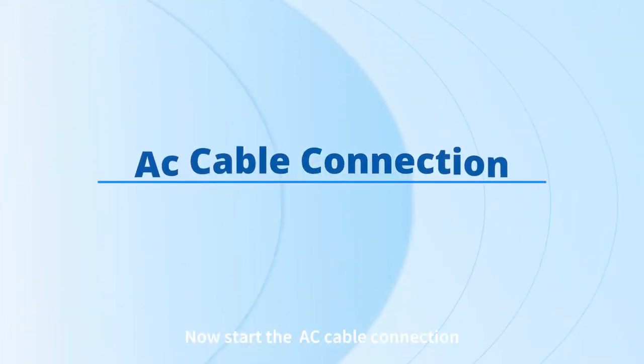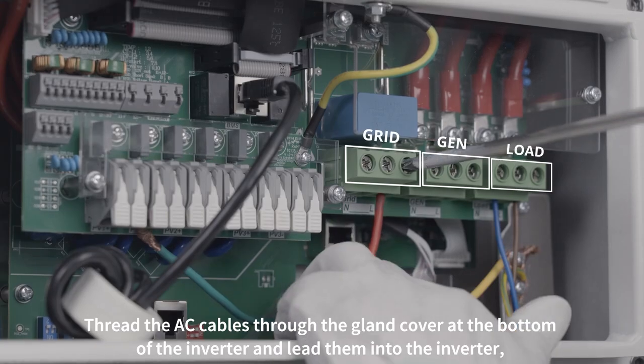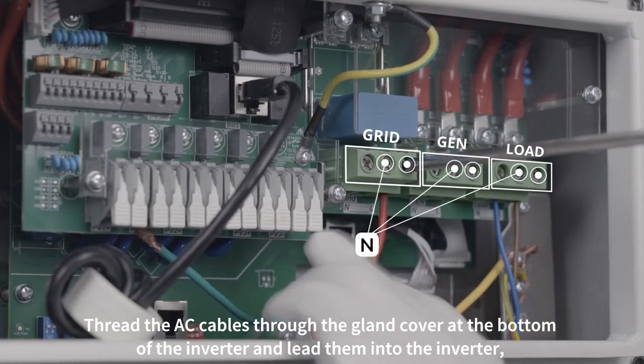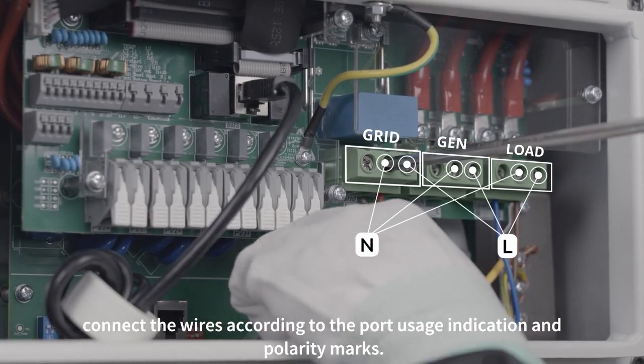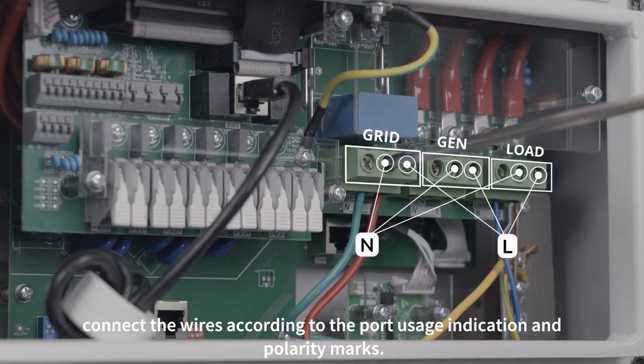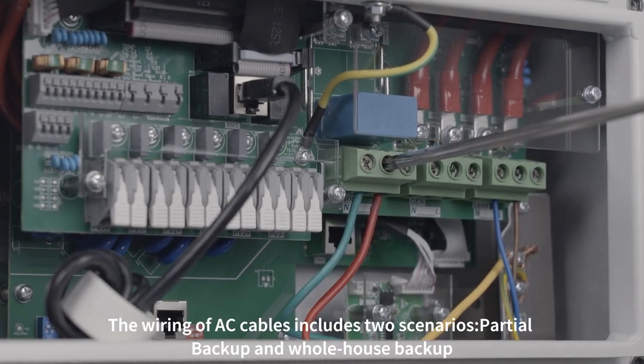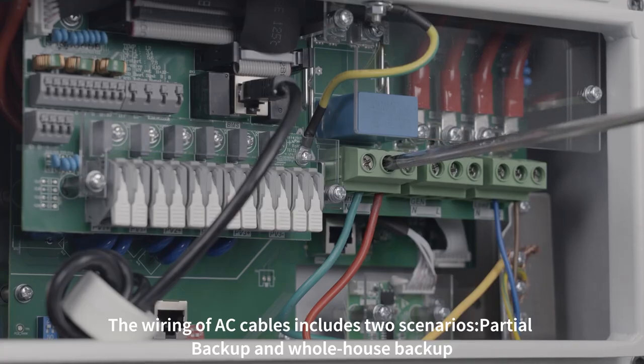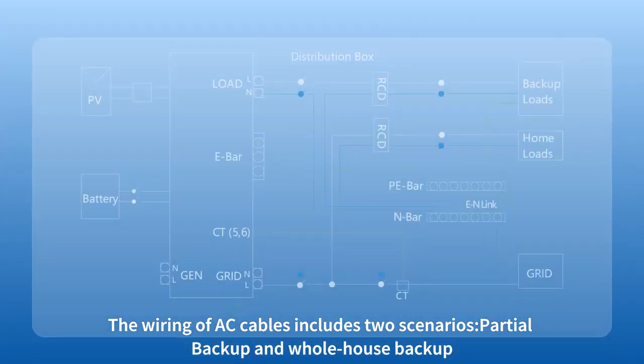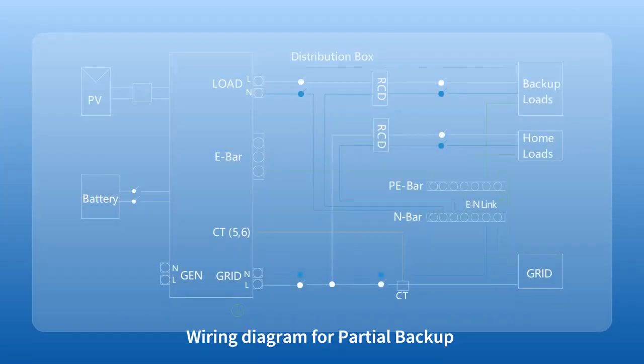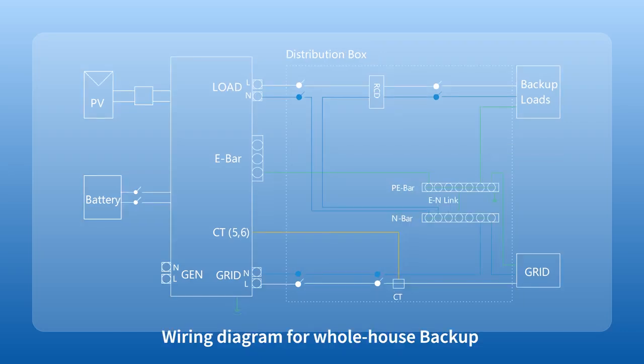Now start the AC cable connection. Thread the AC cables through the gland cover at the bottom of the inverter and lead them into the inverter. Connect the wires according to the port usage indication and polarity marks. The wiring of AC cables includes 2 scenarios: partial backup and whole house backup. Wiring diagram for partial backup. Wiring diagram for whole house backup.